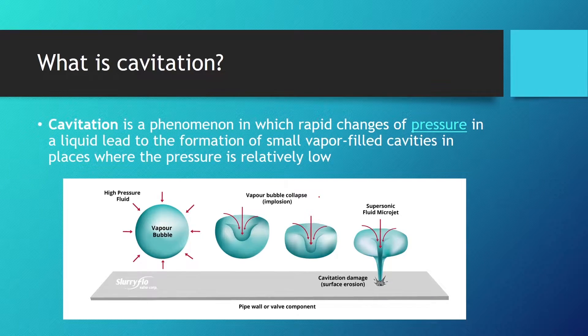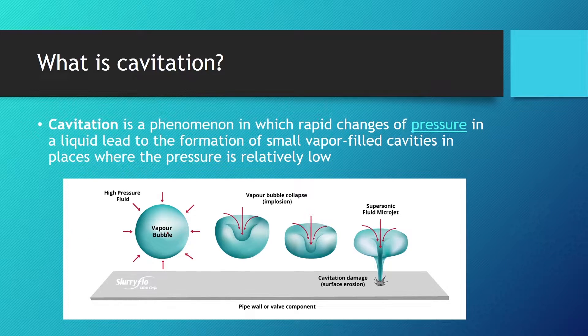What is cavitation? Cavitation is a phenomenon in which rapid changes of pressure in a liquid lead to the formation of small vapor-filled cavities in places where the pressure is relatively low. On the pump's inlet side in hydraulic pumps we have excessive vacuum conditions on the supply side, and that's where cavitation or vapor bubbles are formed. They collapse when they reach a point of higher pressure.